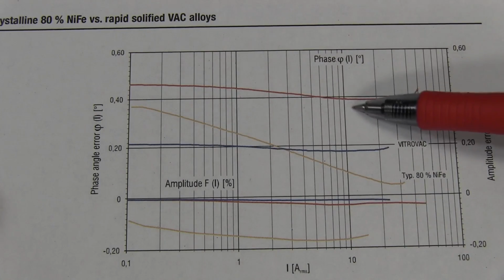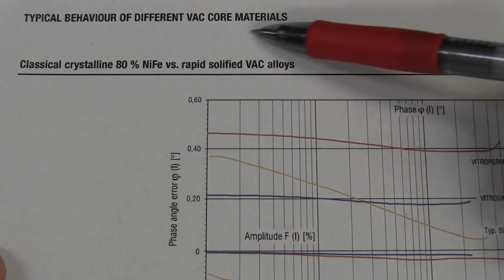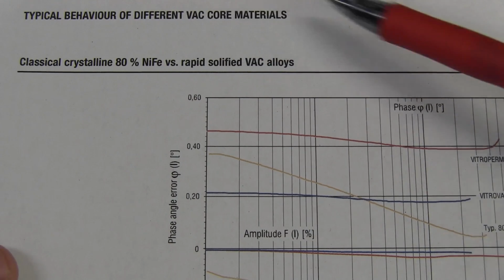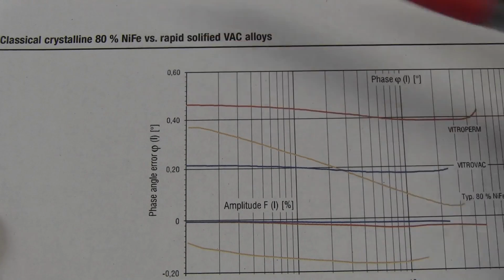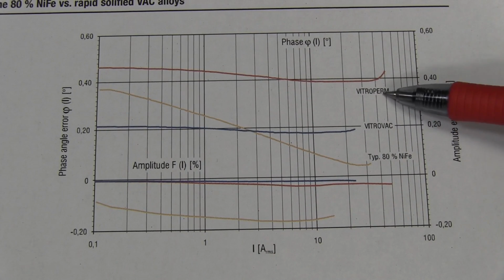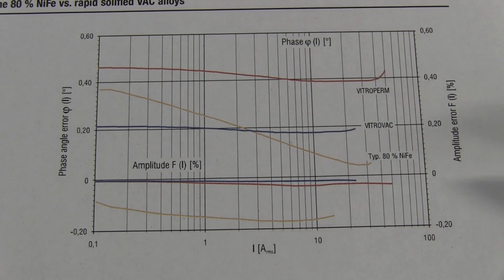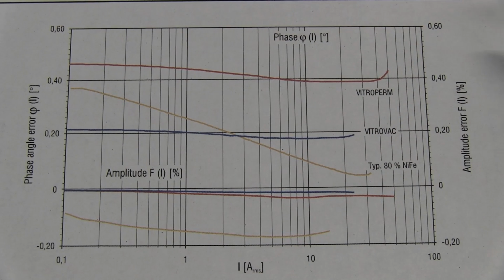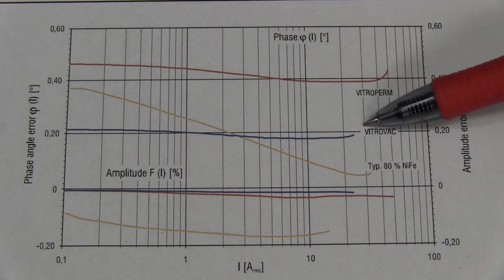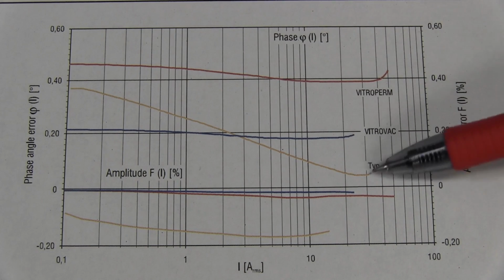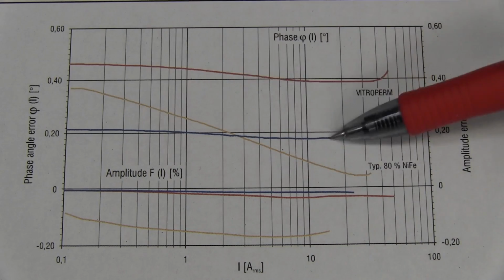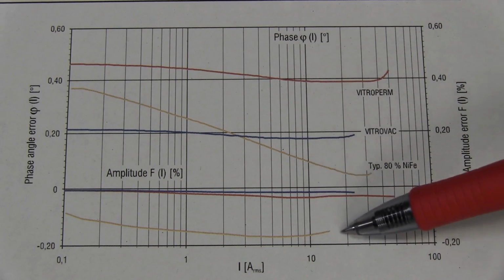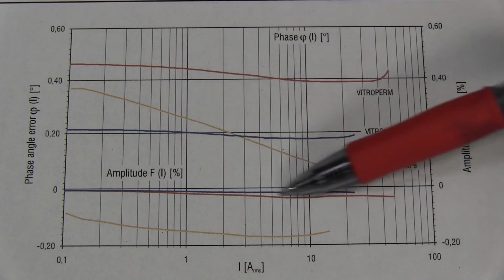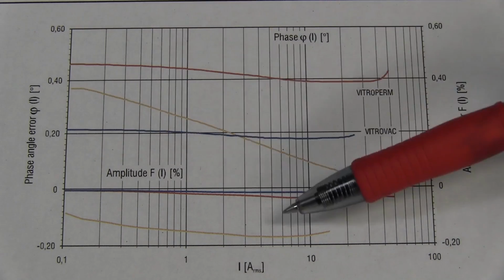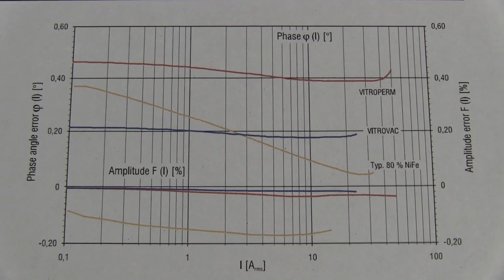Now here's an interesting performance graph. It shows basically the behavior of different types of VAC core materials compared to regular 80% nickel iron cores. They've got their Vitroperm and Vitrovac, trademark terms for their own core material, and they've got an amplitude error here. You can see theirs is basically flat over the full current range compared to a typical 80% nickel iron core. So much more linear using their Vitrovac. Same thing on the phase error as well - look at that, it's pretty much almost flat for the phase angle there compared to the typical 80% nickel iron stuff.